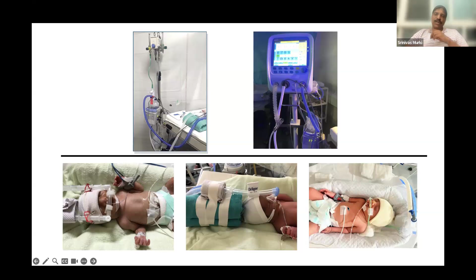So how do we set the knobs? As I said, CPAP is only for oxygenation. It has very little to do with CO2 removal, because CO2 removal happens naturally with the baby's respiratory efforts. So there are only 2-3 knobs which we need. The CPAP or the MAP knob. MAP in HFOV is equivalent to CPAP in a CPAP machine, and FiO2 is the same as FiO2. And to generate the CPAP pressure, you need flows. So flow is almost fixed at 5 liters per minute in most bubble CPAPs, because the pressure required is 5 to 8 or 5 to 9 in most of our CPAP machines. So a flow of 5 liters is quite sufficient for generating that pressure. So we normally keep the flow constant at 5 liters.